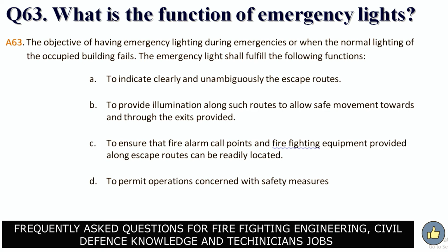Answer. The objective of having emergency light is for use during emergencies or when the normal lighting of the occupied building fails. The emergency light shall fulfill the following functions. A. To indicate clearly and unambiguously the escape routes. B. To provide illumination along such routes to allow safe movement towards and through the exits provided. C. To ensure that fire alarm call points and firefighting equipment provided along escape routes can be readily located. D. To permit operations concerned with safety measures.